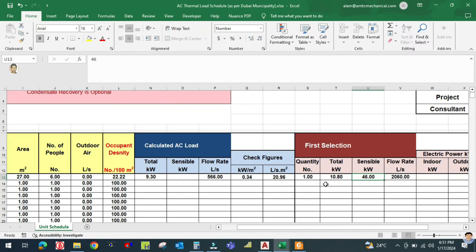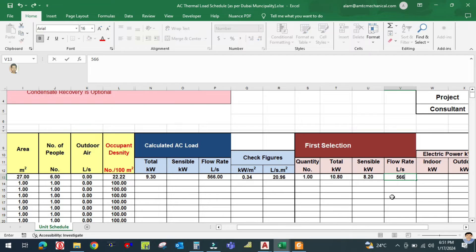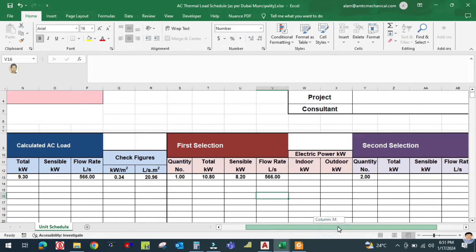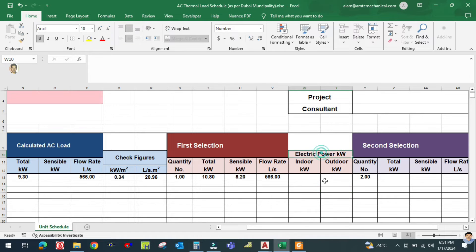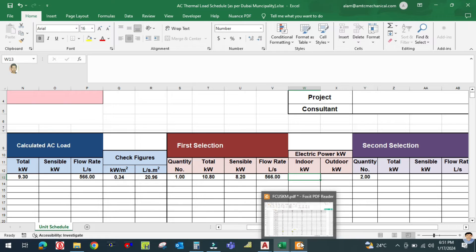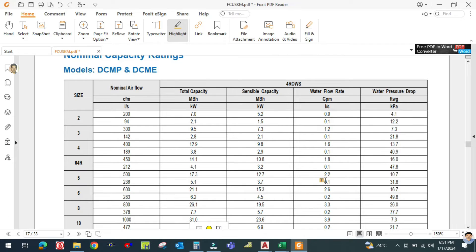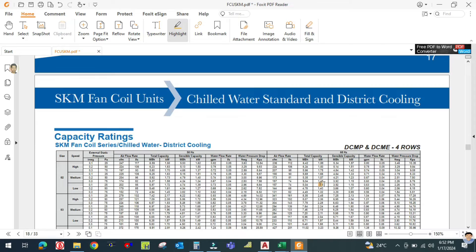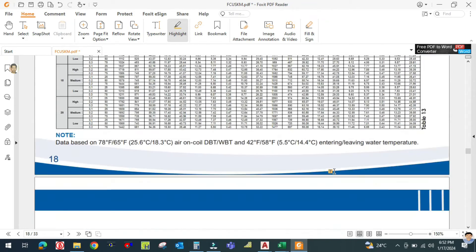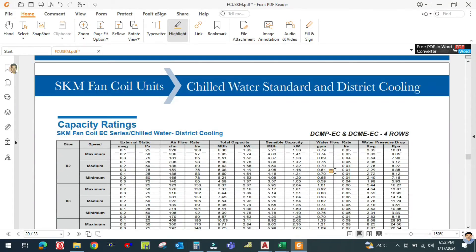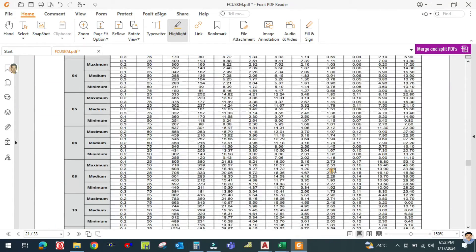The sensible kilowatt for this selected unit is 8.2 kW. The total flow rate remains 566 liters per second. For electrical kilowatts, we look at indoor unit data — since we are selecting an indoor unit, the outdoor chiller will be selected separately based on total indoor load. The electrical data needs to be checked from a separate sheet.